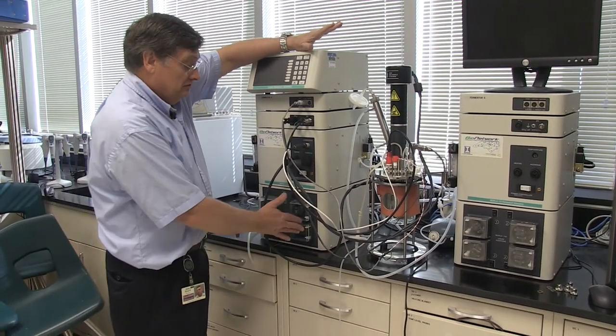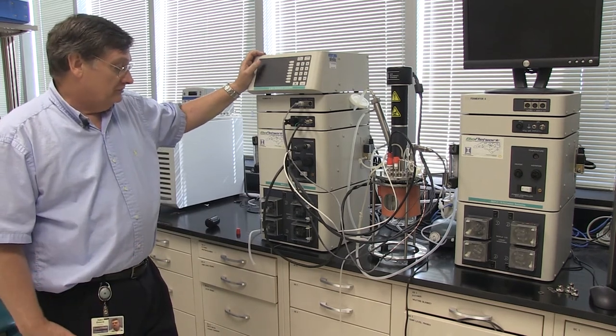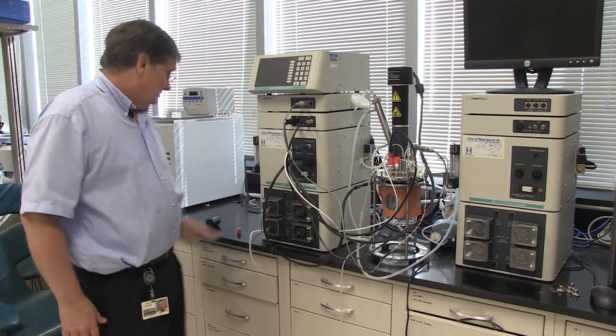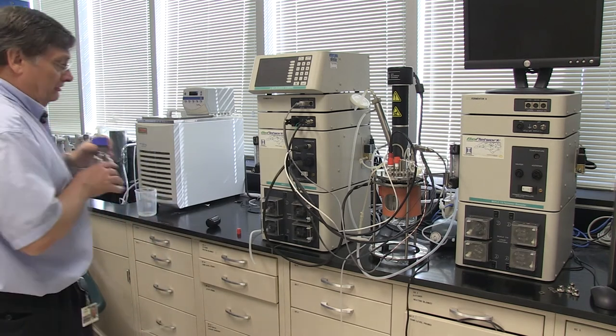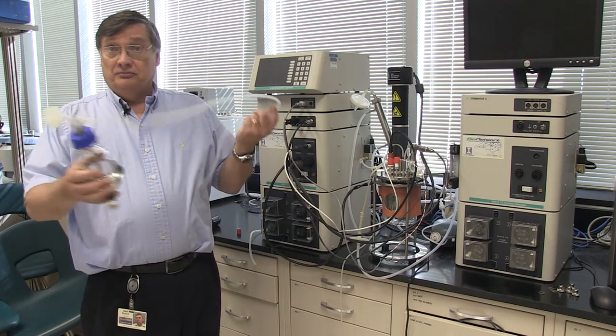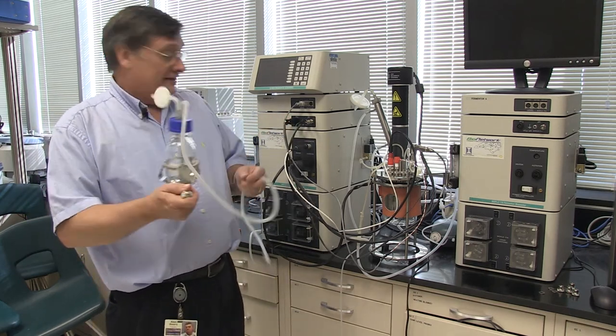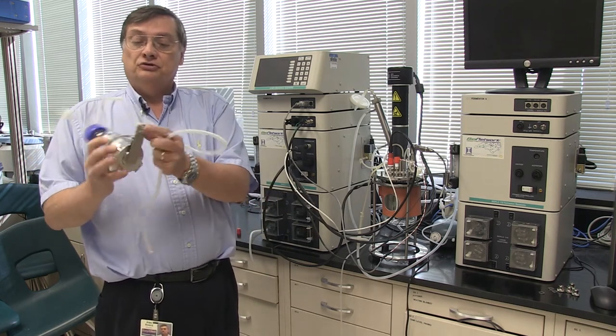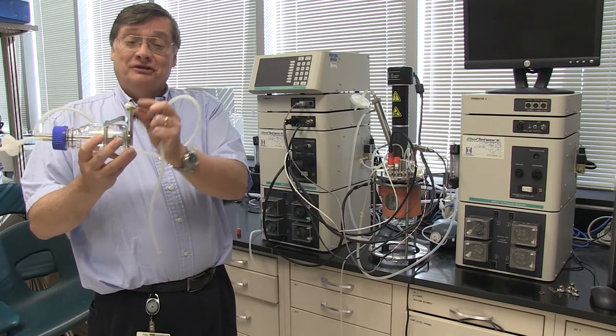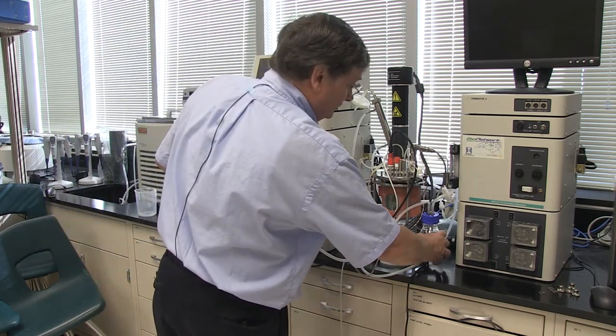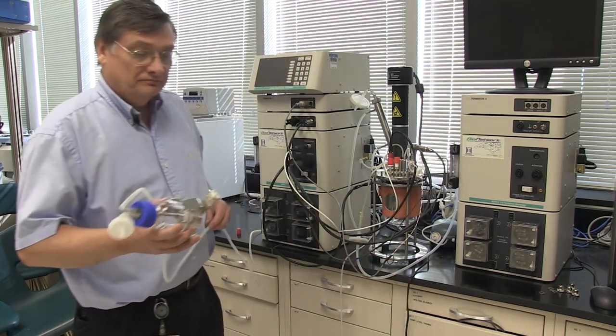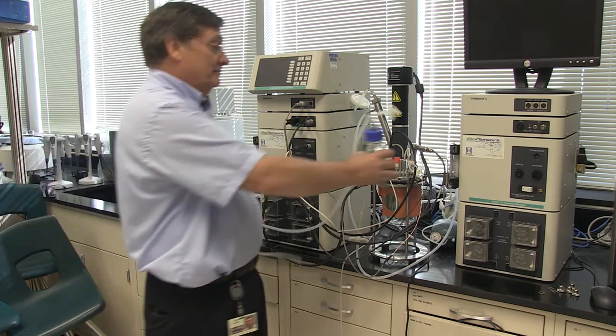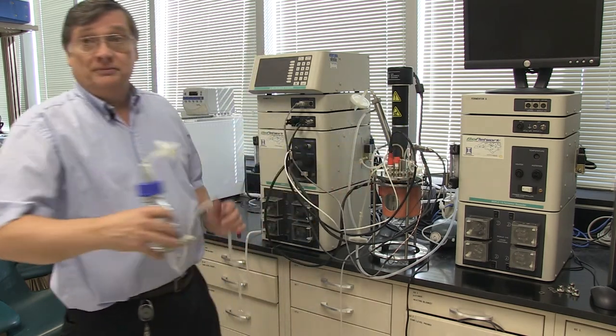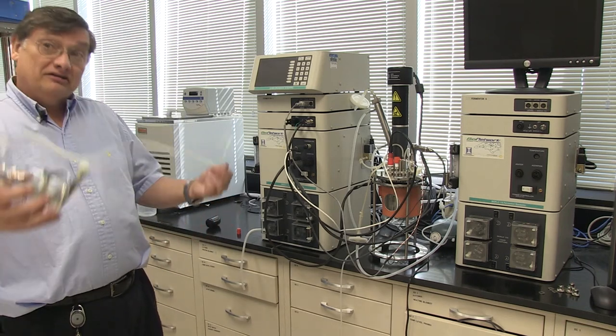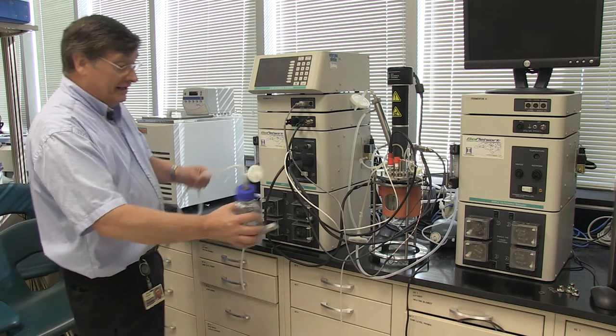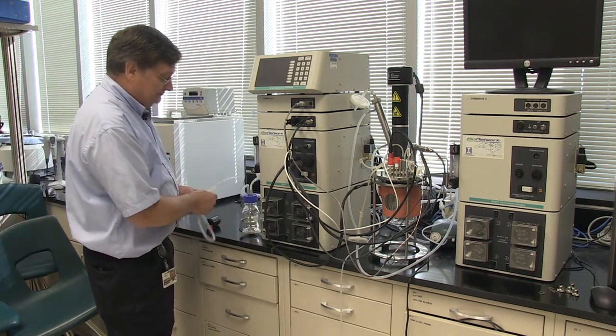Now, there are some other things. Like I said, for instance, if there were anti-foam to control these pumps, or that needed the pumps, then you might have a bottle here. This would be the type of bottle you use for your anti-foam. And actually, they can be autoclaved. See, it's got a little screw here. I've got it taped on there so it doesn't get lost. But you obviously take the tape off, and you could screw it into one of these holes in the bottom of the plate. Or if you take that screw out, you can mount it on the head plate up here so it can be autoclaved along with the vessel. Or you can autoclave it separately. But in that case, you'd have, say, your bottle of anti-foam.